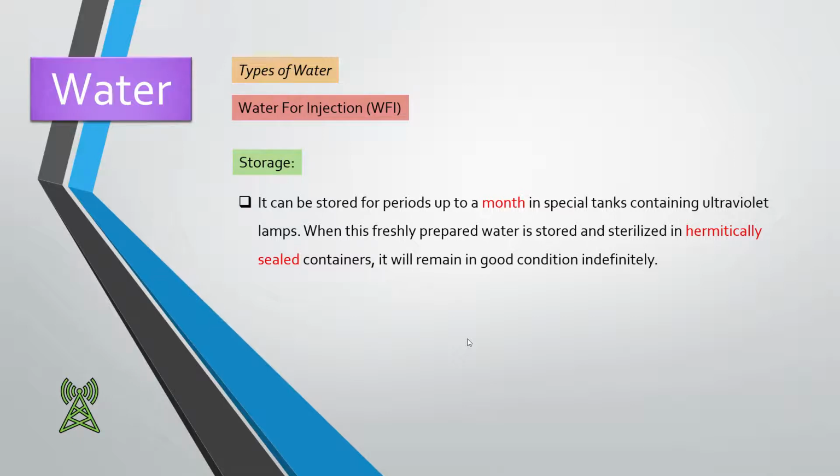So it can be stored in sealed containers and in bulk containers, but in the industry, the main container in which we store water for production of our pharmaceutical batch, that container we have already discussed before these vacations, is kept on circulating. It is maintained at 80 degrees centigrade throughout the period until it is used for the production of the pharmaceutical dosage form.